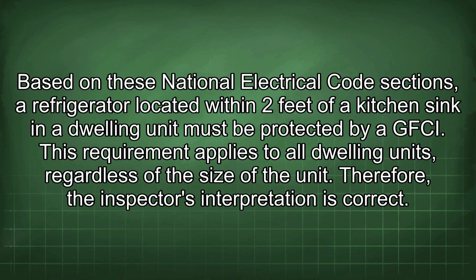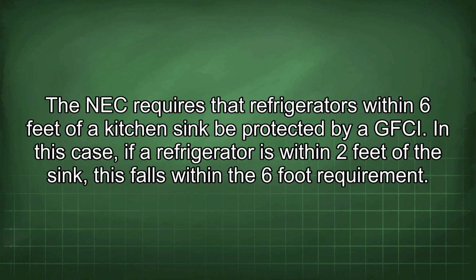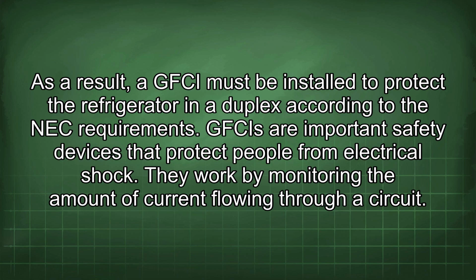This requirement applies to all dwelling units, regardless of the size of the unit. Therefore, the inspector's interpretation is correct. The NEC requires that refrigerators within 6 feet of a kitchen sink be protected by a GFCI. In this case, if a refrigerator is within 2 feet of the sink, this falls within the 6-foot requirement. As a result, a GFCI must be installed to protect the refrigerator in a duplex according to the NEC requirements.